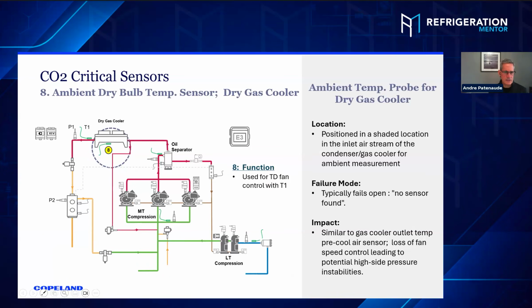And I think this might be one of the last sensors that we're going to look at: the dry bulb on a dry gas cooler, what we see in Canada. It's used to measure TD across that for fan speed control.